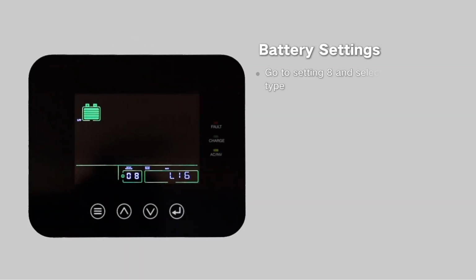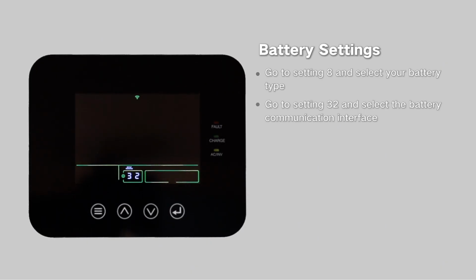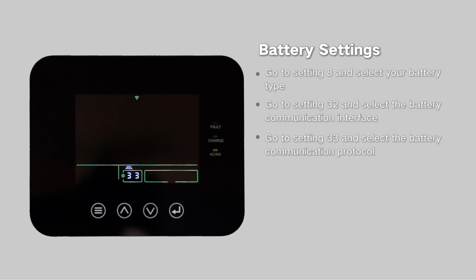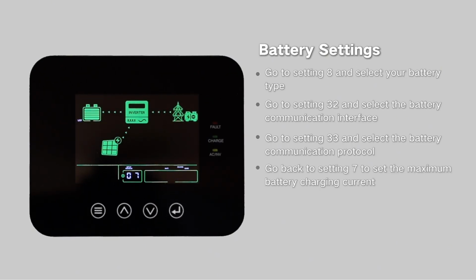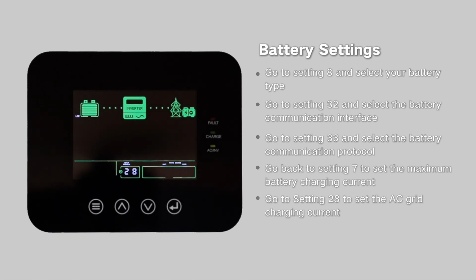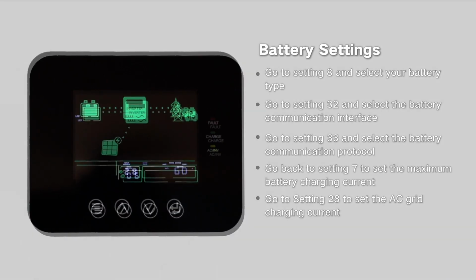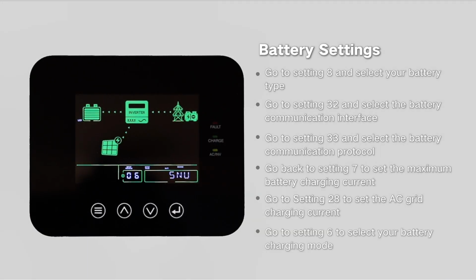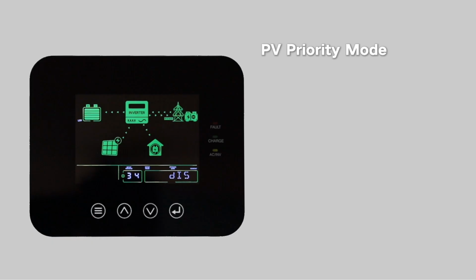Battery settings. Go to setting 8 and select your battery type. Go to setting 32 and select the battery communication interface. Go to setting 33 and select the battery communication protocol. Now, go back to setting 7 to set the maximum battery charging current. Go to setting 28 to set the AC grid charging current. Finally, go to setting 6 to select your battery charging mode, PV priority mode.